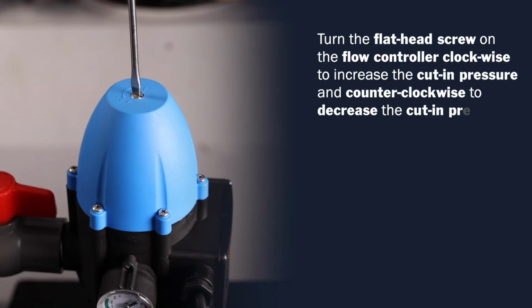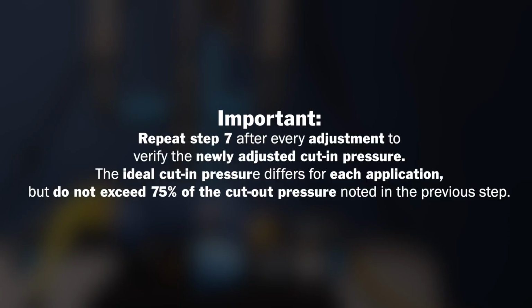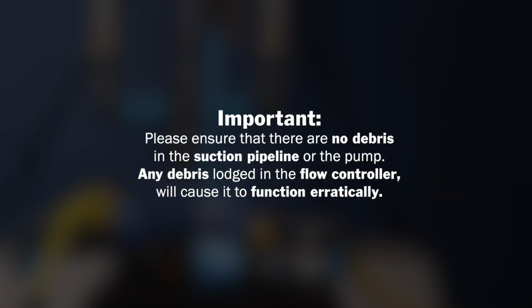Turn the flathead screw on the flow controller clockwise to increase the cut-in pressure and counterclockwise to decrease the cut-in pressure. Repeat step 7 after every adjustment to verify the newly adjusted cut-in pressure. The ideal cut-in pressure differs for each application, but do not exceed 75% of the cutout pressure noted in the previous step. Please ensure that there is no debris in the suction pipeline or the pump.